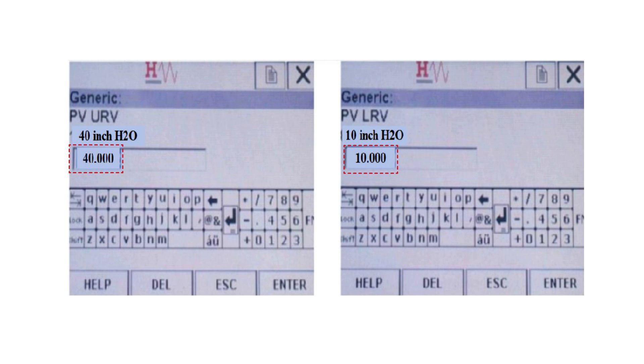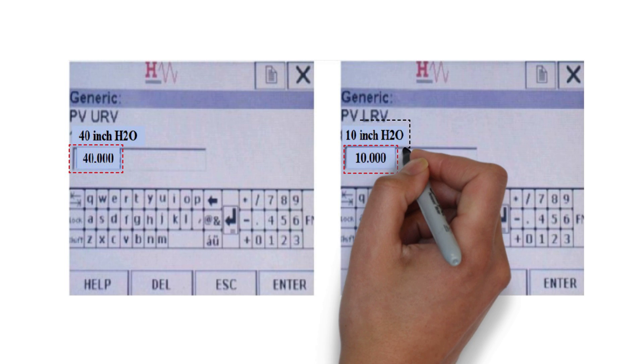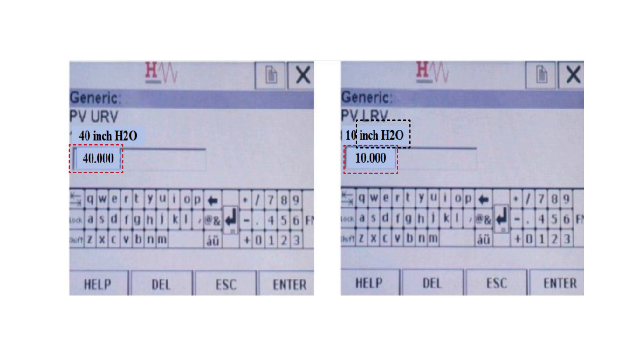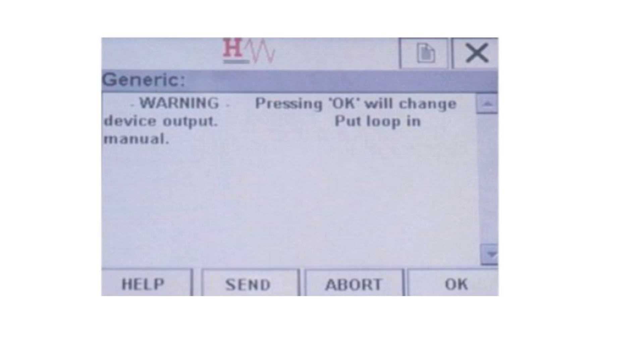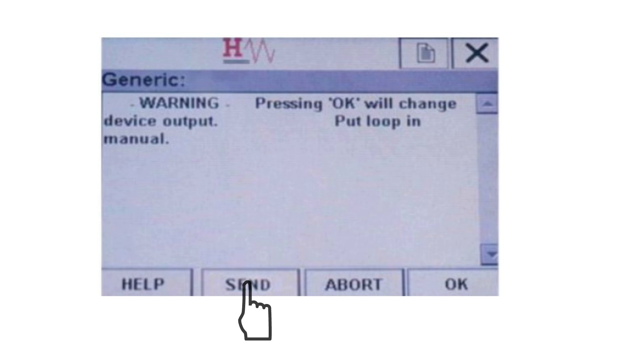The edit screen will allow range to be entered for the URV and LRV as shown in this image. In addition to this, you need to be aware of the unit of measure, which is shown next to the current URV and LRV. In this example, it is inches H2O. After entering the range, press the enter button. Note that the change will not take effect until it is sent to the device, so tap the send button to send the range to the device.